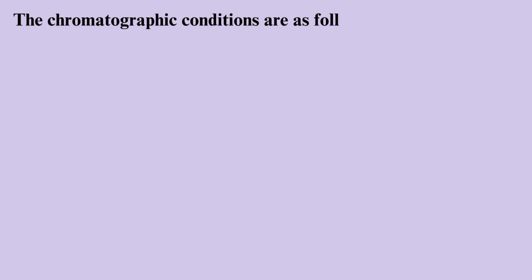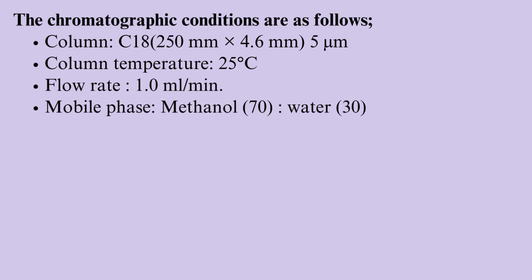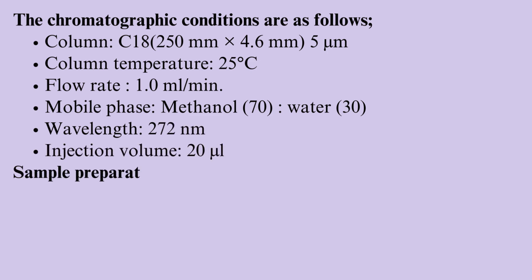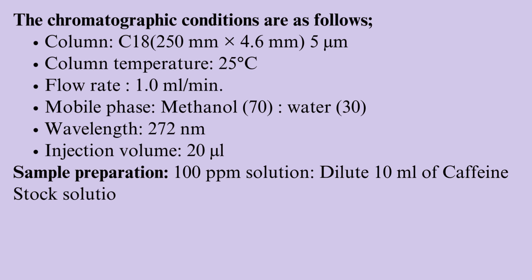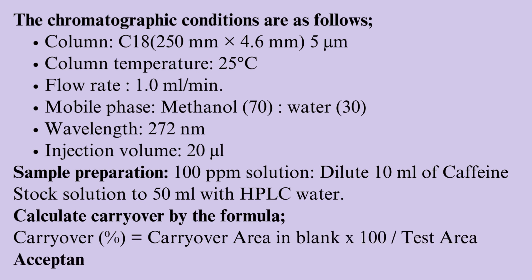Carryover test — chromatographic conditions: column C18, 250 mm × 4.6 mm, 5 µm; column temperature 25°C; flow rate 1 ml/min; mobile phase methanol/water; wavelength 272 nm; injection volume 20 µL. Sample preparation — 100 ppm solution: dilute 10 ml of caffeine stock solution to 50 ml with HPLC water. Calculate carryover by the formula: carryover% = (carryover area in blank × 100) / test area. Acceptance criteria: not more than 0.01%.